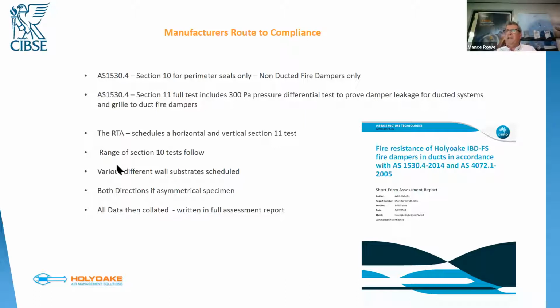But just to recap, AS 1530.4 section 10 is for perimeter seals only. There's a number of products out there in the marketplace that purport compliance with AS 1530.4, but when you drill down through the detail, you find they're only compliant with section 10, and I've seen them connected to ductwork. So that's a real trap out there. Section 11 is the full test, which includes the 300 Pascal pressure differential test. Right, it's the RTA that schedules the horizontal and vertical section 11 test, and then a range of section 10 tests tend to follow.